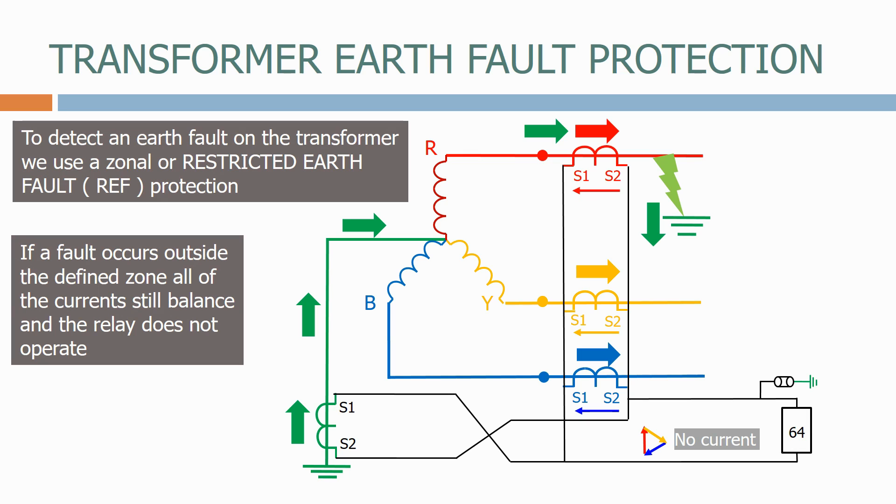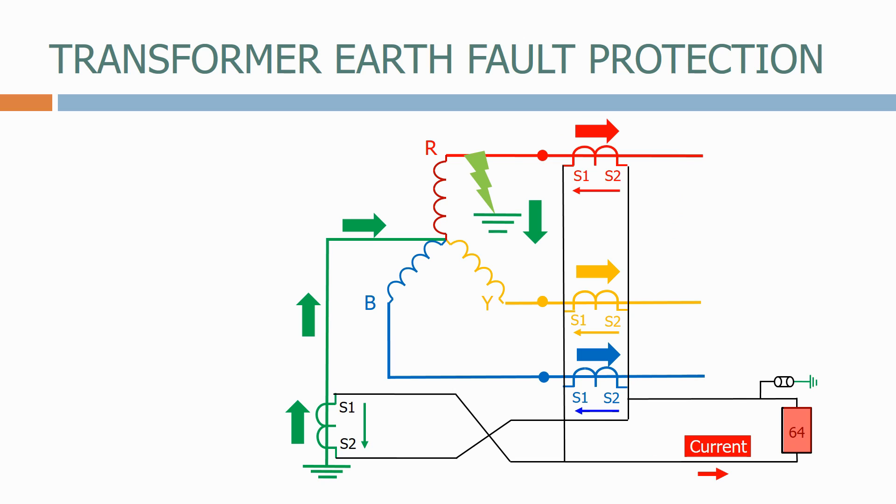Let's now remove the fault and apply a fault inside the zone on the transformer itself. This time there is no earth fault current generated on any of the phase CTs, but we do have current flowing through the CT on the ground connection. This imbalance will cause a spill current which is enough to operate the earth fault relay.